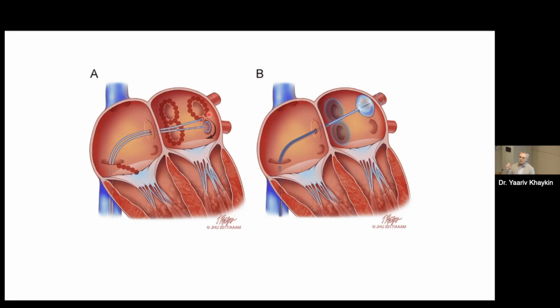The very small surface area at the contact between the tip of the catheter and the tissue creates a lot of resistance to electron flow that increases the temperature in the tissues. We want that temperature to go up above about 50 centigrade. That causes denaturation of proteins and cell death.